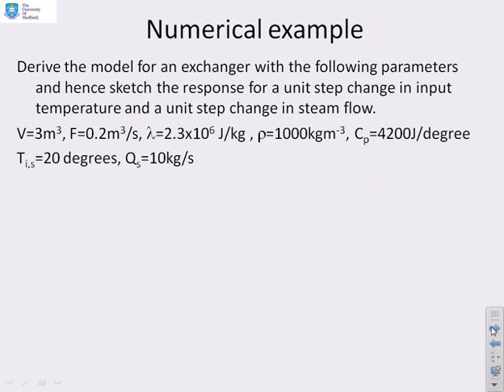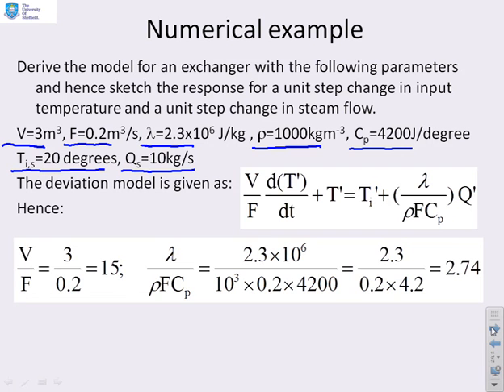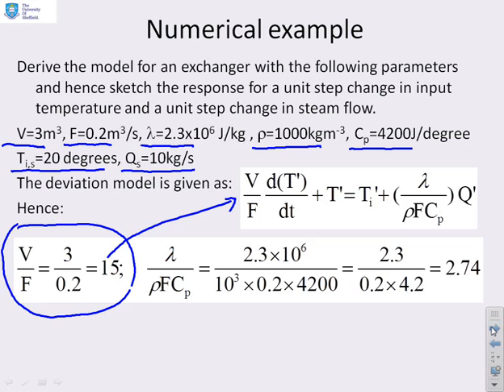Let's look at a numerical example. We've been supplied with the following data: volume V = 3 m³, flow rate F = 0.2 m³/s, latent heat lambda = 2.3 × 10⁶ J/kg, density rho = 1000 kg/m³, specific heat C_p = 4200 J/(kg·°C), steady state inlet temperature = 20°C, and steady state steam flow = 10 kg/s. We need to substitute all those numbers into the model. Using deviation variables, we first calculate V over F: that's 3 over 0.2, which is 15. We then need lambda over rho F C_p, and putting all the numbers in gives 2.74.